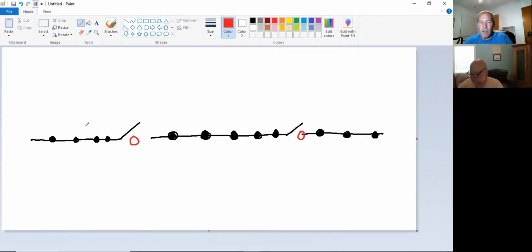We'll say the left is energized here, and the right is de-energized, because it's open, right? Gentlemen, a visual open point is defined as an air gap, or an open point that you can visually see where the connection is broken. Inside a breaker in a substation, you can't see that. It's encased. Inside switchgear, that's for underground, you can't see that open point until you see an air gap in between.